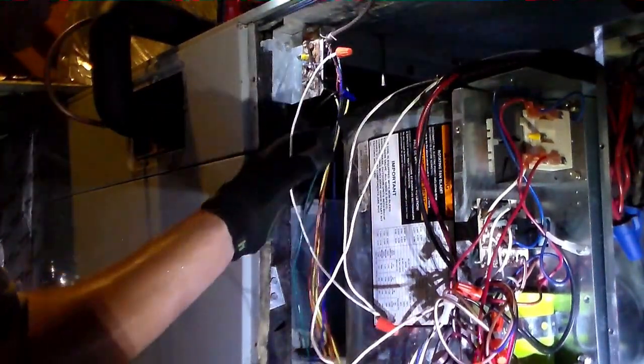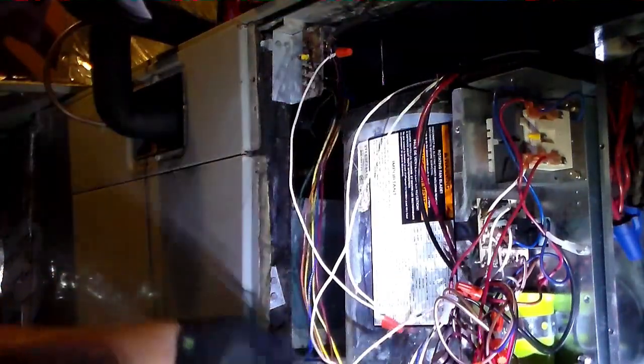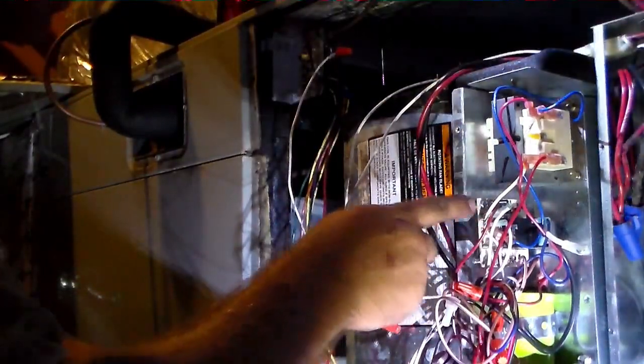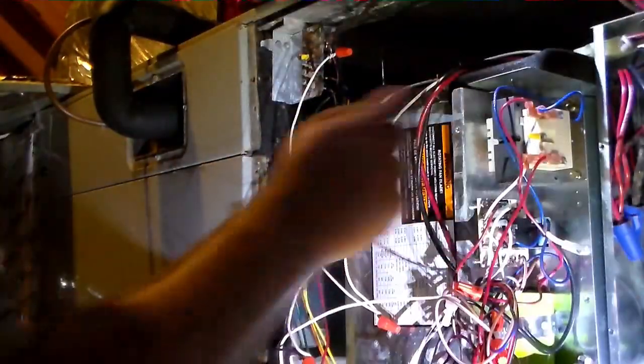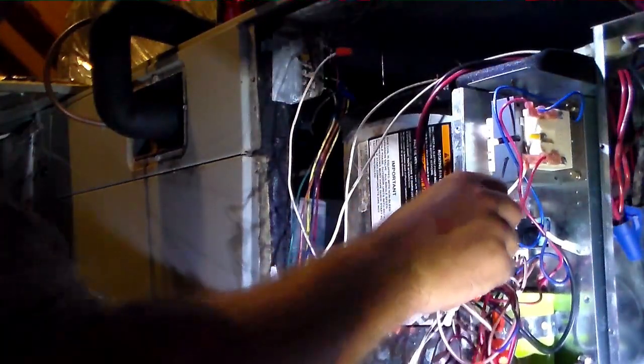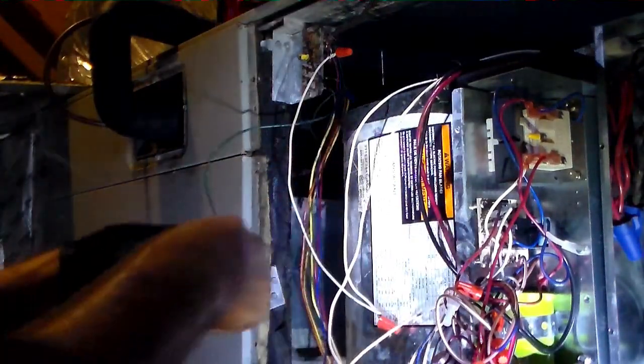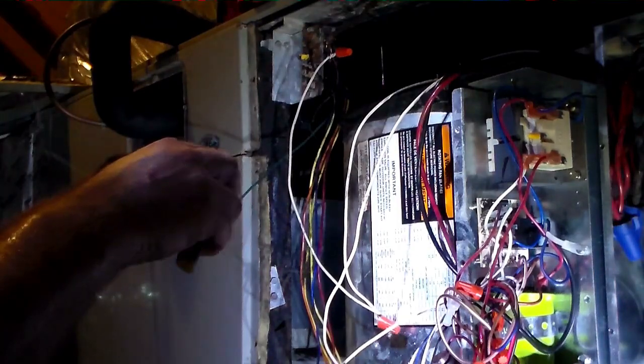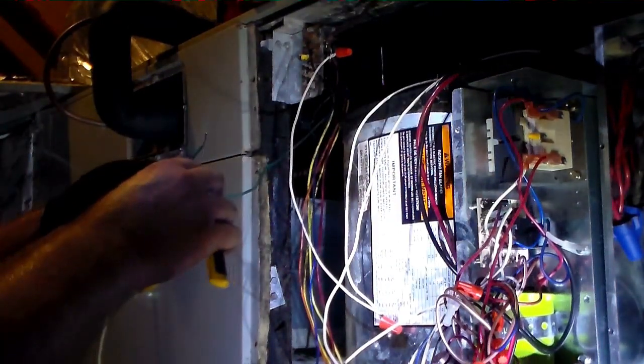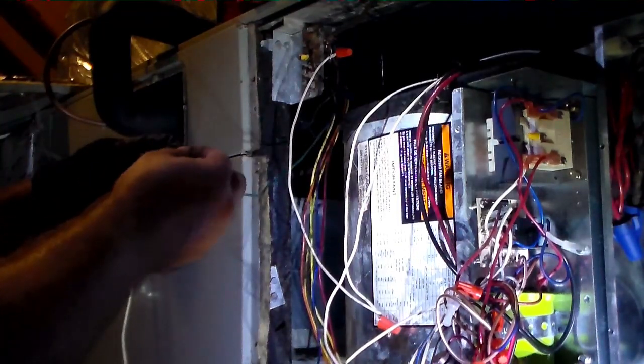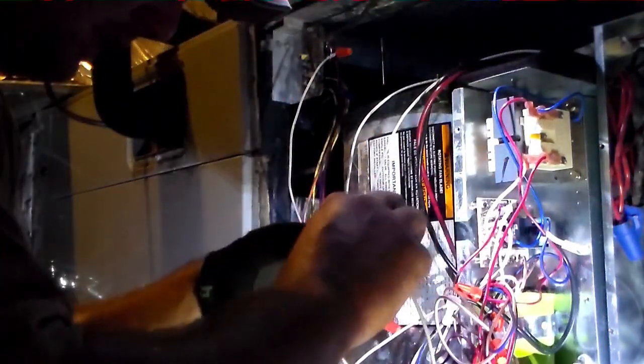Alright, so we have our red going to the transformer and zone board. We have our common going both to the contactor and back to the fan control board, and then by extension goes back to the transformer. Our green is the only one left, and that'll be traveling back to fan control board. I'll stuff it backwards just to make sure it'll fit. So I have a stake on the other end, just in case it doesn't fit. It's tight, because we've been cramming lots of wires.